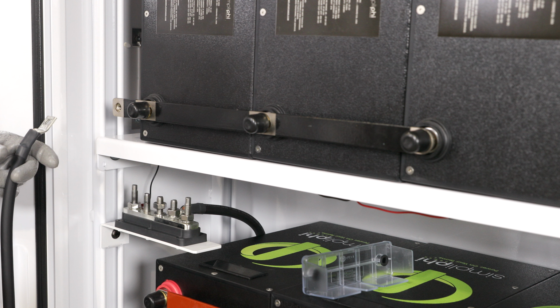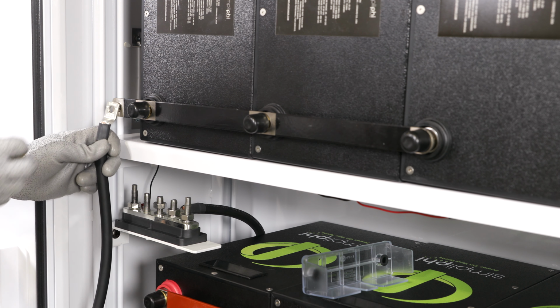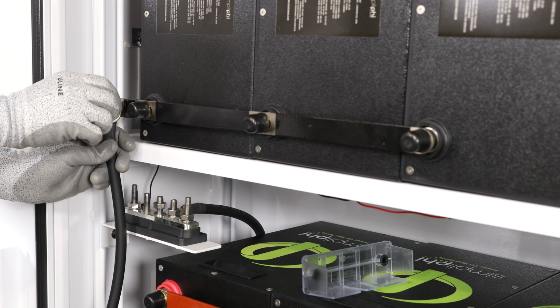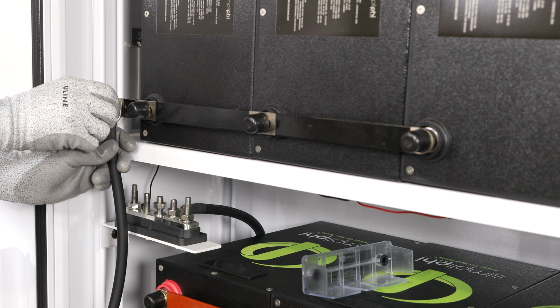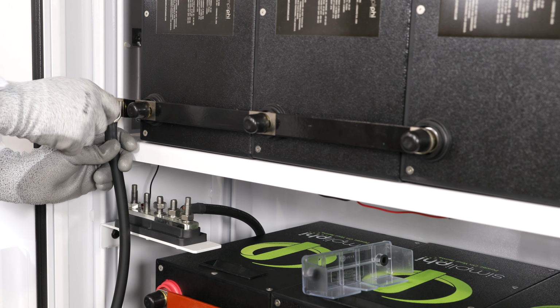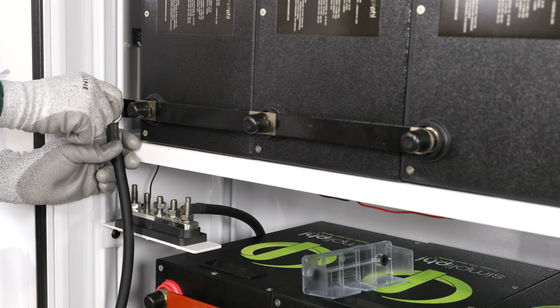We will land the top shelf negative bus bar to the terminal block post, second in from the left. Attach the cable at a 90-degree angle when securing it to the bus bar. Angle the cable so it extends directly down towards the 5-point terminal block. This allows the cabling to be routed more easily.